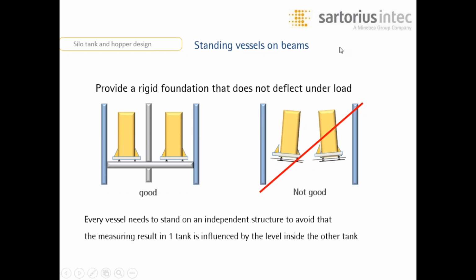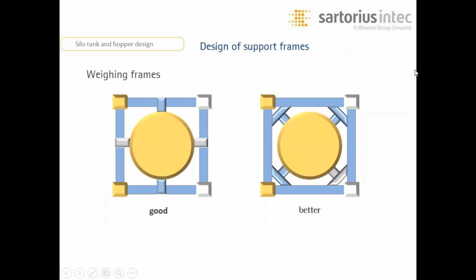Weighing frames, design of a support frame. On the left, you can see the frame looking at it from the top. You can see how it's pretty good. You can have the 4 load cells mounted on the outside perimeter of the system. But the one on the right shows that each one of them is actually being supported better and is providing more rigidity for the actual base itself. Weighing frames should be made in the stiffest way possible. Additional beams reduce the bending and therefore increase the accuracy of the entire system.